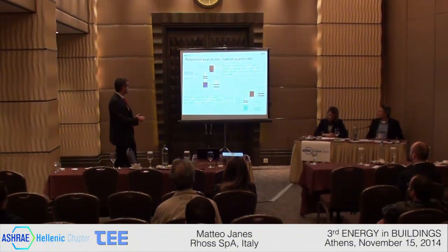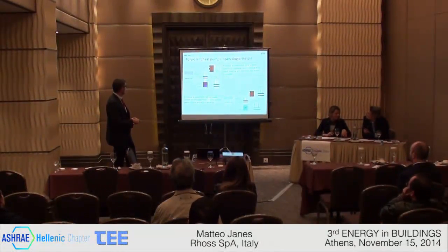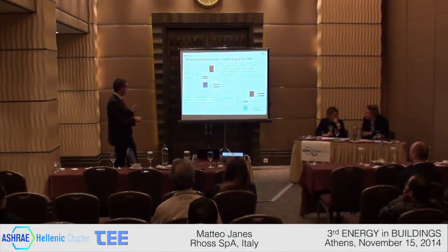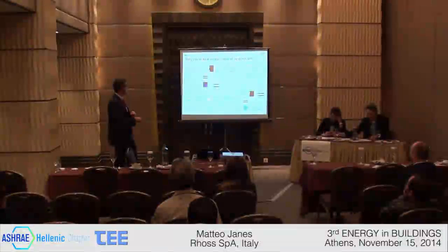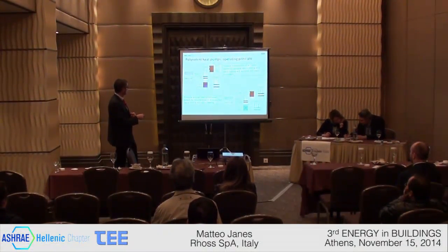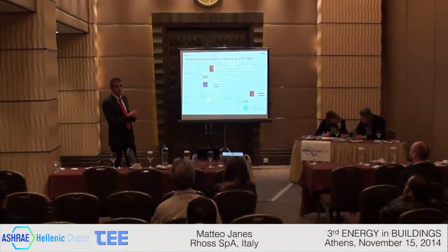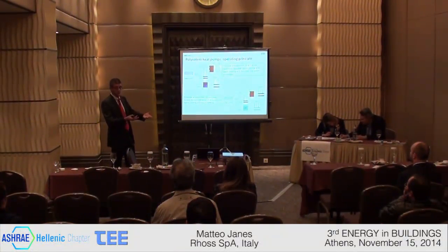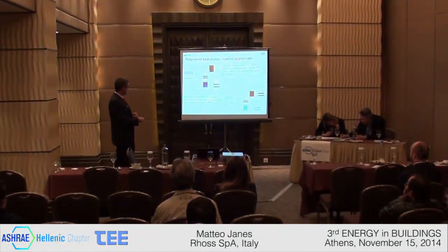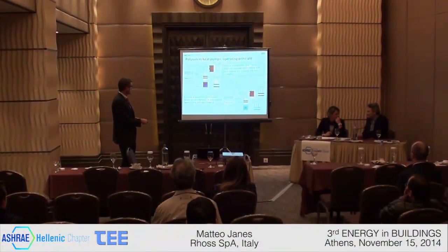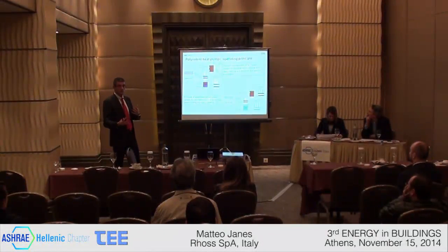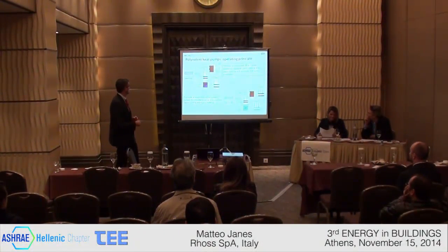This is the typical principal arrangement of a 2-pipe system, where the main heat exchanger is connected to the air conditioning system and is producing chilled water in summer and hot water in winter. And the heat recovery is connected with the domestic hot water circuit and can be used to produce domestic hot water. This is the principal arrangement for a 4-pipe system, where we need only space cooling and space heating. In this case, the main heat exchanger is connected to the space cooling circuit, the heat recovery to the space heating circuit, and simultaneous or independent cooling and heating are possible.